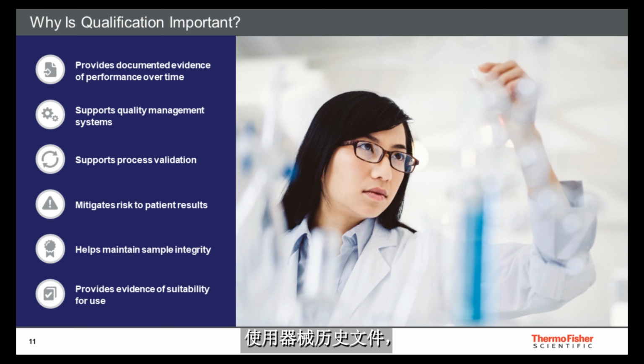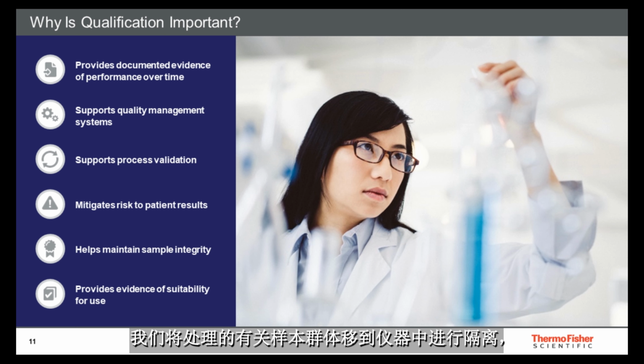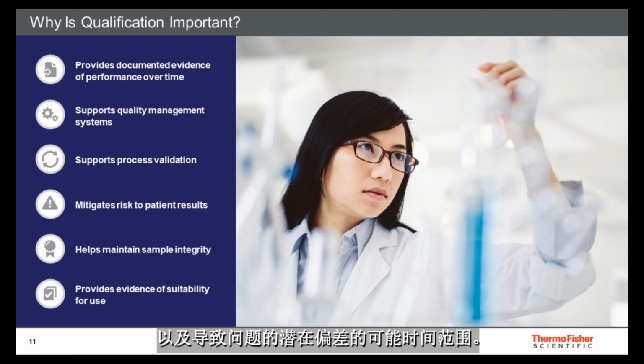Using the device history file, we segregated the sample populations in question, processed to one instrument, and the possible time frame of the potential deviation that caused the injury. Reviewing the qualification in the device history file, the lab showed that the last qualification of the instrument was still in specification. A subsequent qualification of the instrument performed during the investigation showed it was still in specification, thus ruling out the instrument and the samples processed adjacent and subsequently to the sample in question. The investigation ultimately concluded with sample contamination as a cause for the missed result.